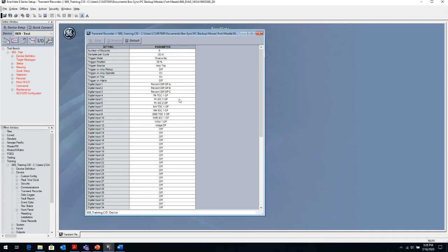So if this is an 889 with a differential protection in it, then there's 2 sets of CTs, maybe a VT and maybe an auxiliary VT. You want it set up to, obviously, the trigger source. You want to set it up to trip, so any trip is able to generate that oscillography. And additionally, maybe there's other elements. Maybe you also want to set up on pickup.